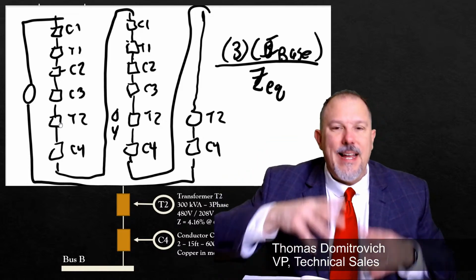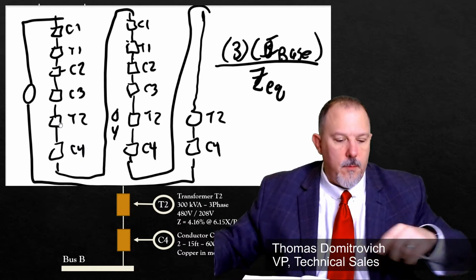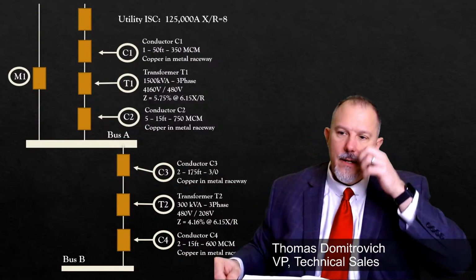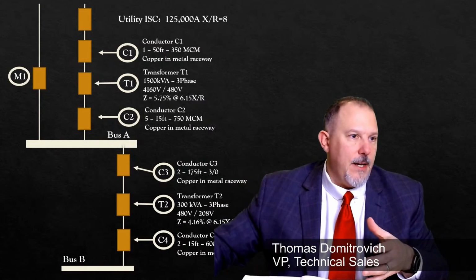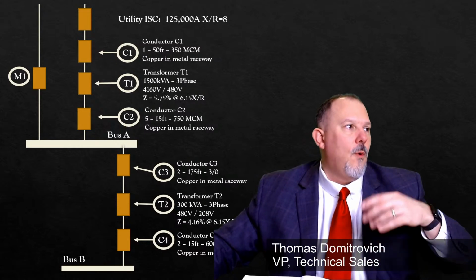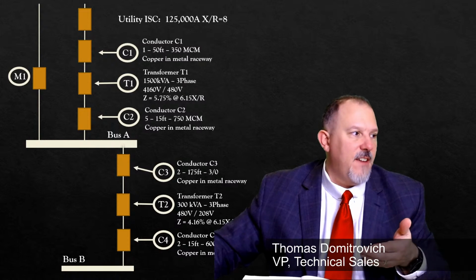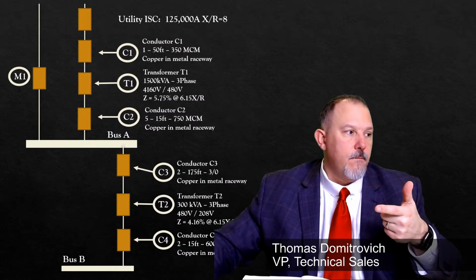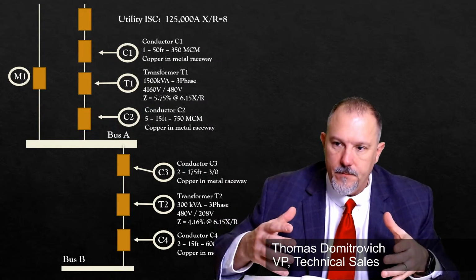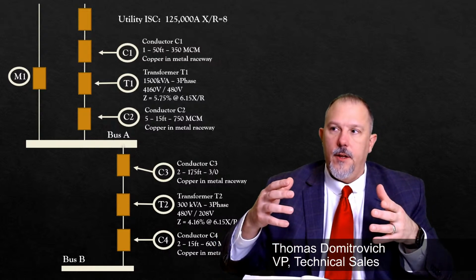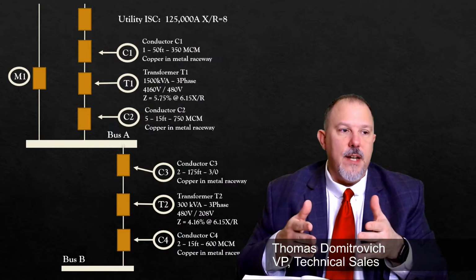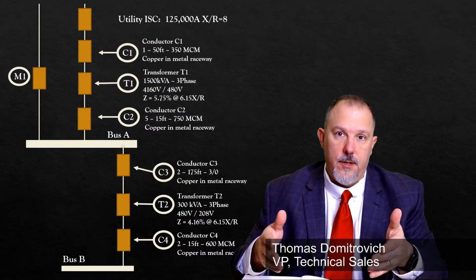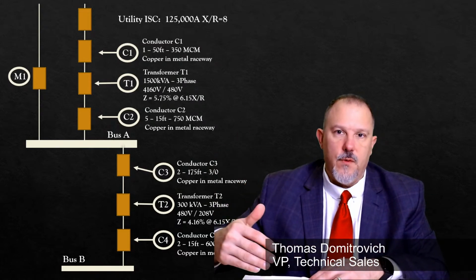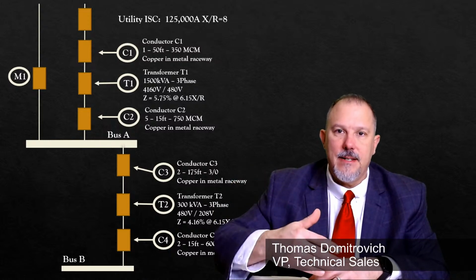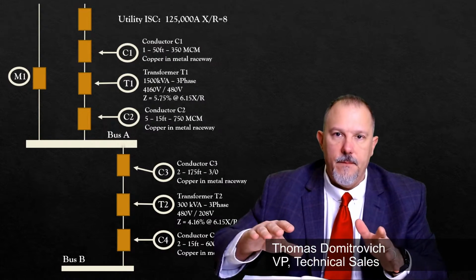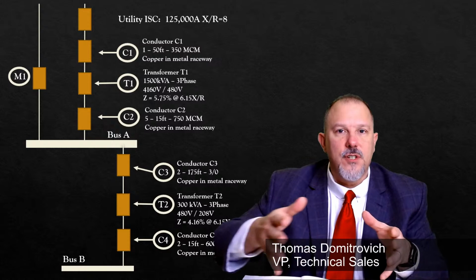So I should, technically. Let's talk about the impedance of the transformer. That transformer has a 5.75% impedance, right? The question basically is, why didn't I take 10% off the 5.75% impedance of the transformer? I should have. When we calculate short circuit currents, we're looking for interrupting ratings. So both of these transformers should have been modeled at minus 10%. I didn't do that because I didn't want to complicate the math. And from an educational perspective, it's layers of information.